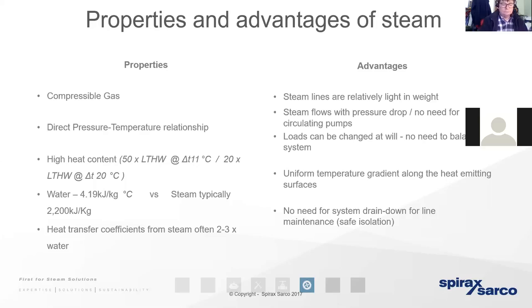Steam as a gas gives up its heat energy and condenses evenly and equally across the entirety of the heat transfer surface area. Also, the speed of heat transfer — the heat transfer coefficient — can be three times greater than on a water-to-water heat exchanger. Those are just some of the key advantages of using steam for heat exchange as opposed to any other source of heat energy.